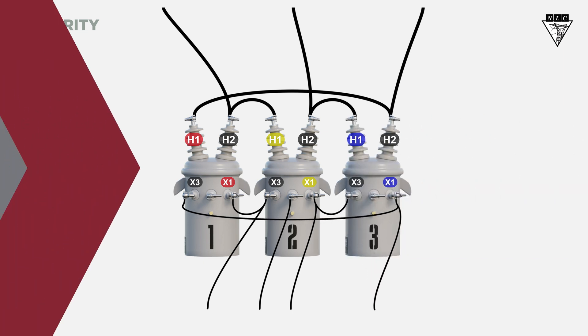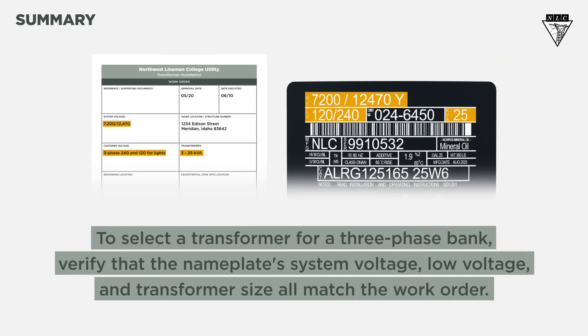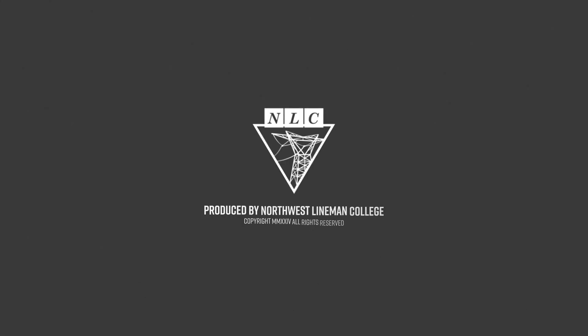So, what did we learn? To select a transformer for a three-phase bank, verify that the nameplate's system voltage, low voltage, and transformer size all match the work order. The impedance and polarity of each transformer you bank together should match. Remember to always check your voltage and rotation according to company procedures. Thanks for watching this Northwest Lineman College tutorial. Work safe out there.